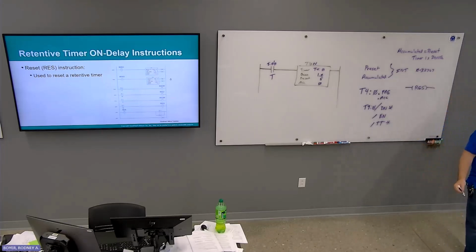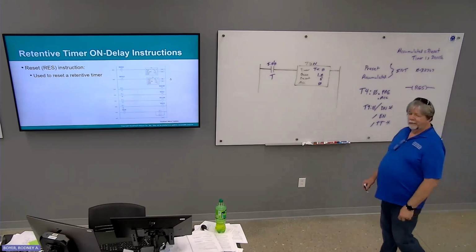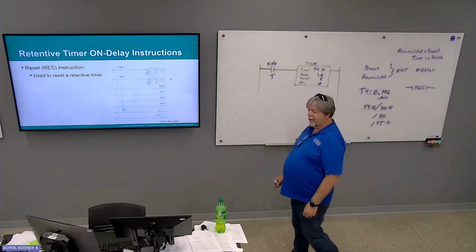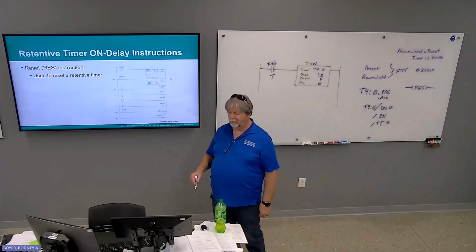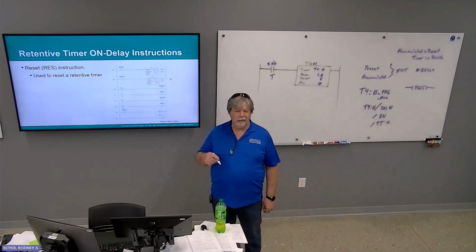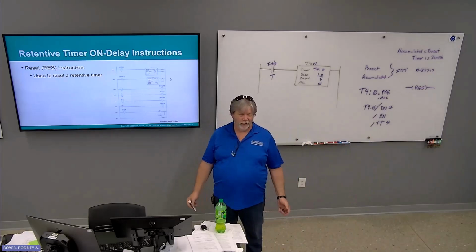Like that, RES for reset. That is not an OTE instruction that is labeled RES. I can tell you how many times I've seen that over the years. That is an actual reset instruction. It is not an OTE instruction that's labeled reset or RES. Okay.